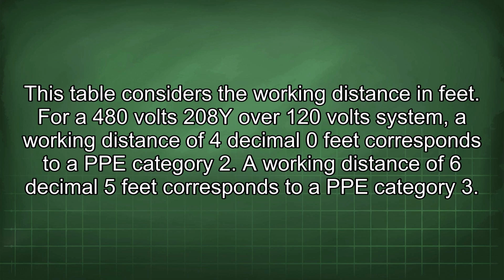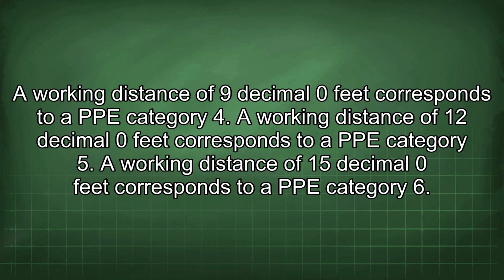For a 480 volts 208 Y over 120 volt system, a working distance of 4.0 feet corresponds to a PPE category 2. A working distance of 6.5 feet corresponds to a PPE category 3. A working distance of 9.0 feet corresponds to a PPE category 4. A working distance of 12.0 feet corresponds to a PPE category 5. A working distance of 15.0 feet corresponds to a PPE category 6.